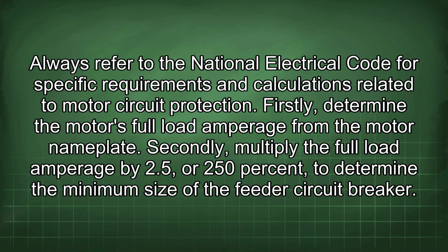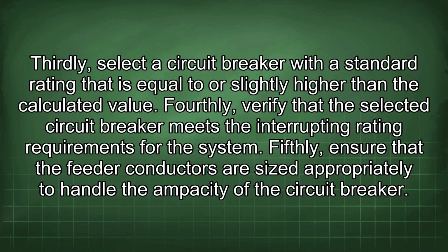Firstly, determine the motor's full load amperage from the motor nameplate. Secondly, multiply the full load amperage by 2.5 or 250% to determine the minimum size of the feeder circuit breaker. Thirdly, select a circuit breaker with a standard rating that is equal to or slightly higher than the calculated value. Fourthly, verify that the selected circuit breaker meets the interrupting rating requirements for the system. Fifthly, ensure that the feeder conductors are sized appropriately to handle the ampacity of the circuit breaker.